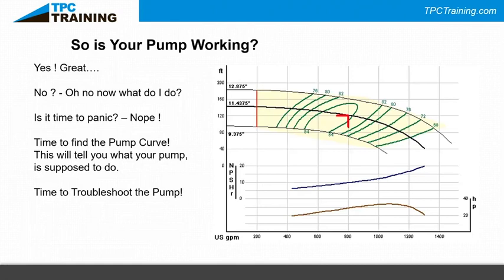That's the thing people have a hard time grasping. When it was all over I asked how long the old pump had lasted — about 11 or 12 years. But that pump used to be three or four hundred feet away from the tank. When they added onto the plant and got three-phase power near the tank, they moved the pump right next to it. A lot of pump problems crop up after something changes in the system — and people don't redo the friction calculations to understand what the pump is now capable of doing.